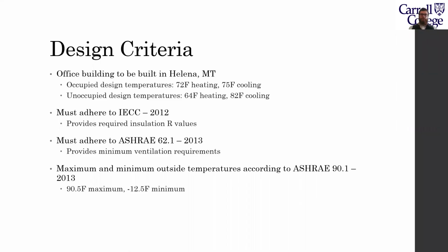The occupied design temperature for the building is 72 heating and 75 cooling, and the unoccupied design temperatures are 64 heating and 82 cooling. The building adheres to the International Energy Conservation Code, which provides insulation R values, and also adheres to ASHRAE 62.1, which provides the minimum ventilation requirements. The building will also be able to operate at the maximum and minimum outside design temperatures according to ASHRAE 90.1. For this region, the maximum outside temperature is 90.5 degrees and the minimum is minus 12.5 degrees.